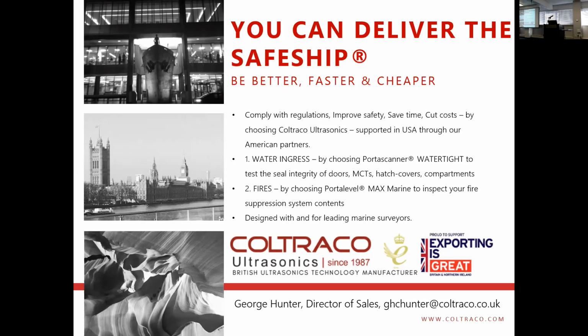I was just wondering, your CO2 unit, the one that measures the CO2, can it also identify powder in hand portable extinguishers and or other cylinder type extinguishers? So powder is an interesting one that has eluded us for many years. We can function on some, but it's the same with foam. We can work on some, but not all. Because we just cannot guarantee it, we never market it as such, and we keep that as very specific. But this equipment really is designed as a liquid level indicator as opposed to a solid level indicator, so I wouldn't recommend it as a core application.